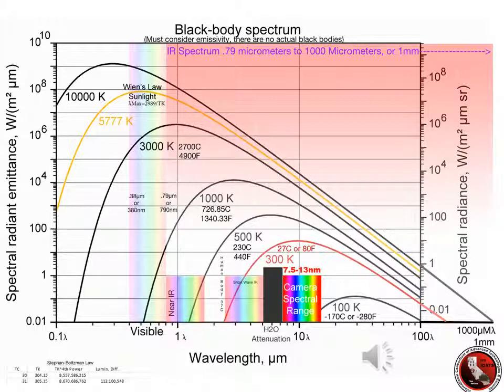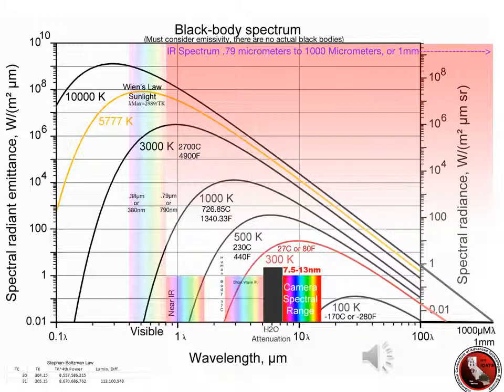Working in thermography on a Navy ship — the USS Kitty Hawk — a technician asked us to look at the elevator contacts. These were massive steel components with a lot of energy flowing through them, weighing 50 to 60 pounds. As we were starting up the old liquid-nitrogen-cooled camera, I looked down and the object was already glowing red. At that point we knew it was over 950 degrees Kelvin, because that's where red light starts to be given off.